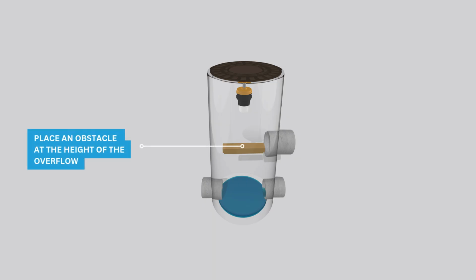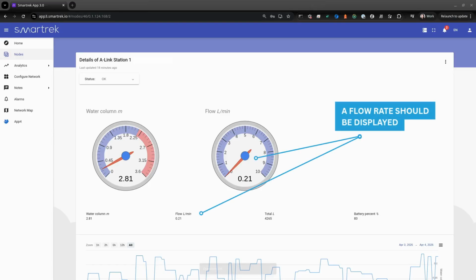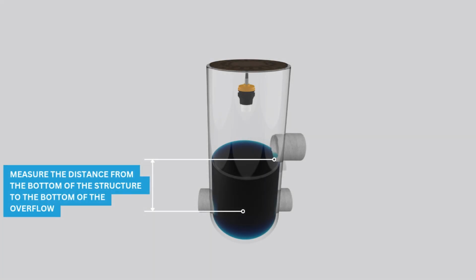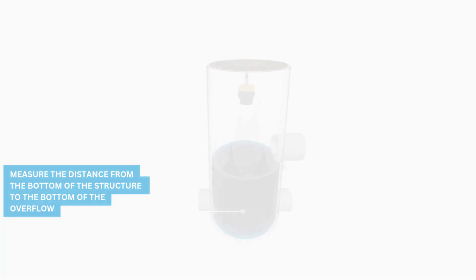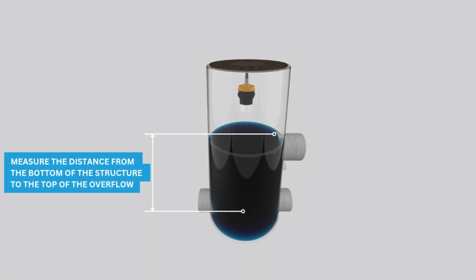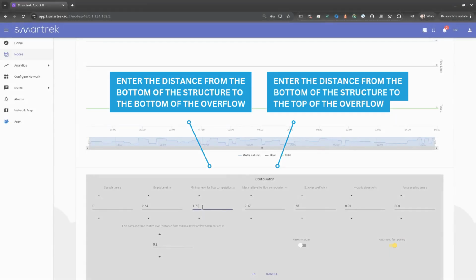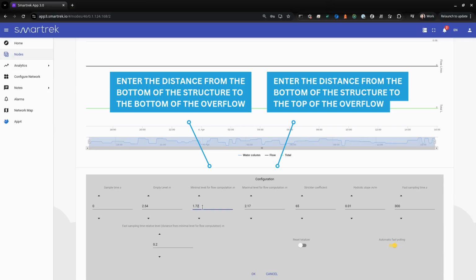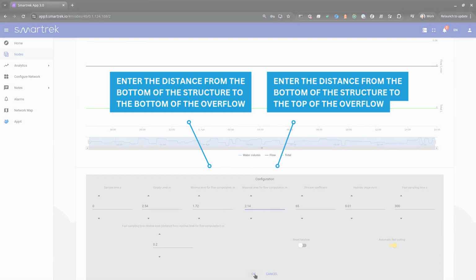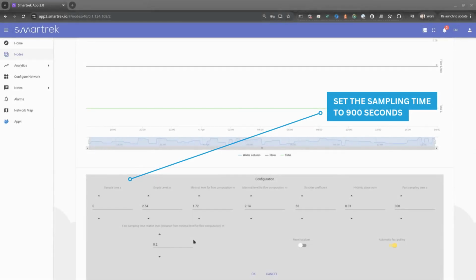Next, to simulate an overflow, place a piece of wood under the probe at the height of the weir. The sensor should detect an overflow and measure a flow rate. If it doesn't, then measure the distance from the bottom of the structure to the bottom of the weir. Do the same for the top of the weir. Enter these two values in the minimum level for flow calculation and maximum level for flow calculation fields. Now that you've finished configuring your sensor, set the sampling period back to 900 seconds.